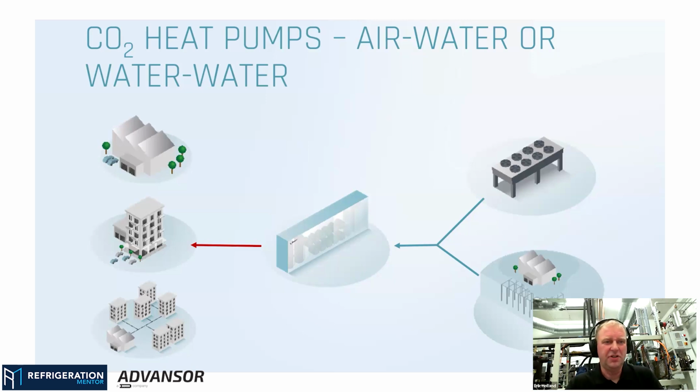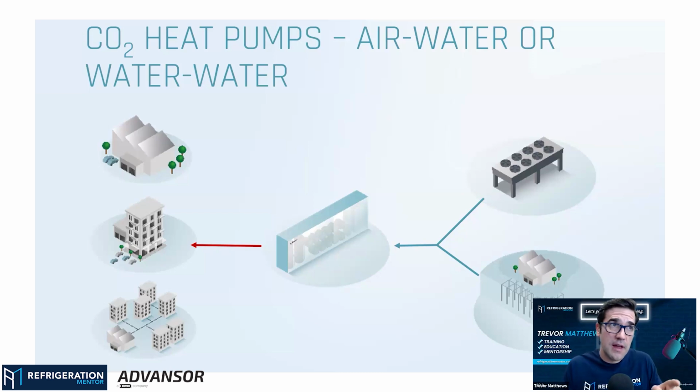So there's all the safety functions, all the basics of how you load your compressors and all that stuff is basically the same. There's no difference. So if you know your groundwork, it's not a big step to go into heat pumps. Yeah, but that's the thing: are you as a technician or a contractor getting into CO2? It's no different than what you were installing for the last 20 years. Those processes need to be the same. You're pulling an evacuation down below 200 microns, making sure you pressure test everything by your codes and standards, making sure you test all the inputs and outputs.